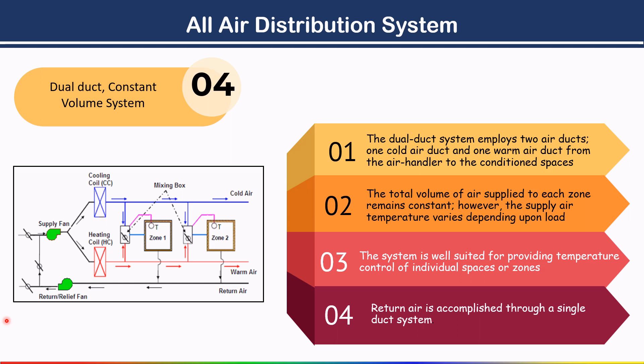The total volume of air supplied to each zone remains constant; however, the supply air temperature varies depending upon loads. This system is well suited for providing temperature control of individual spaces or zones. Return air is accomplished through a single duct system.